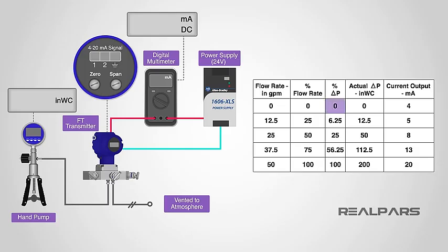Apply the 0% input pressure value, which for us is 0 inches water column, to the transmitter and adjust the zero until we get an output current of 4 milliamps. Apply the 100% input pressure value, which for us is 200 inches water column, to the transmitter and adjust the span until we get an output current of 20 milliamps. Repeat the steps until adjustments are no longer required. Now that you've recalibrated, it's a good idea to apply all of the values from the calibration table and record the corresponding output current values.